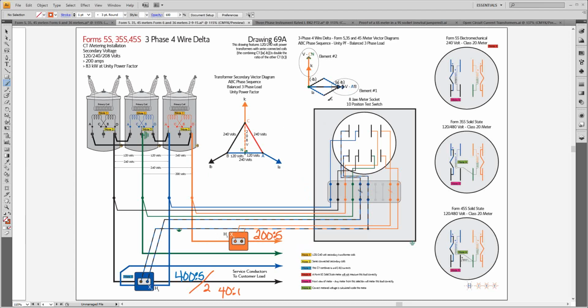And so looking at the vector diagram here, for the transformer connection and for a three-phase load, this is the transformer vector diagram. If you have these drawings that you purchase through the Meterman's Bible, something just to be aware of is the color code of these inside vectors that make up the delta shape here. This blue vector, and the red one and the black one, those are the transformer coils color coded. And so the blue vector would be this coil, the red vector would be this coil, the black vector would be this coil.